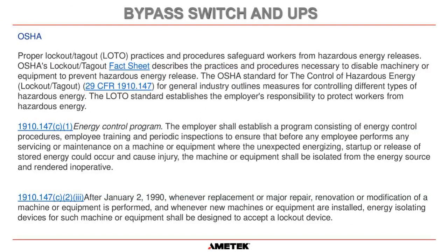So what are the electrical implications of that? Well, OSHA states that proper lockout tagout, or LOTO, practices and procedures should be used to safeguard workers from hazardous energy releases. The control of hazardous energy standard is 29 CFR 1910.147 for general industry, and it outlines measures for controlling different types of hazardous energy. And obviously, LOTO is the standard that everybody uses.